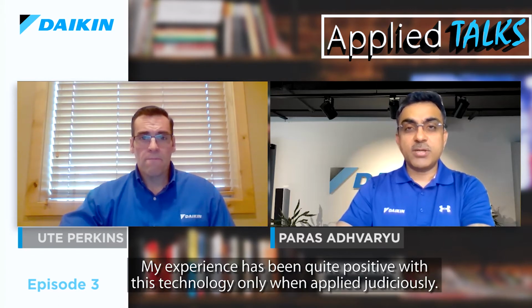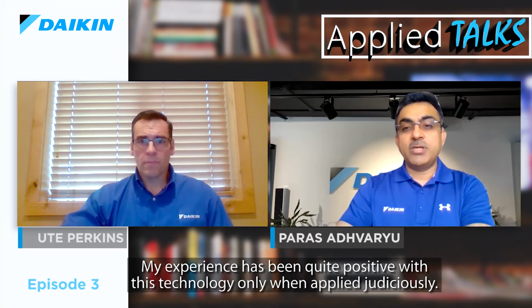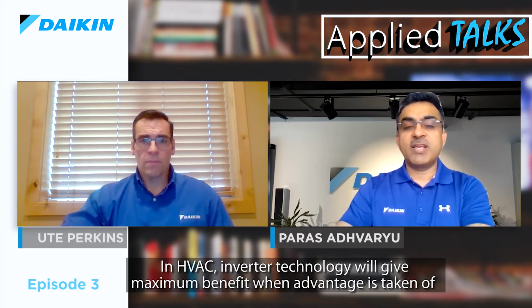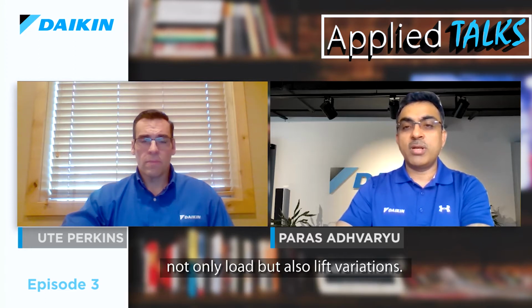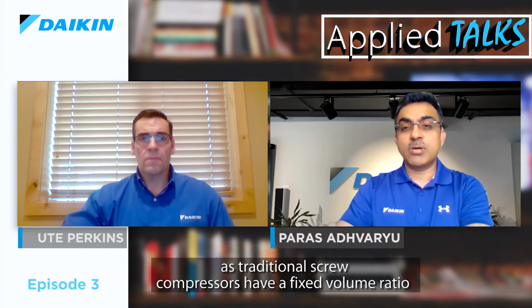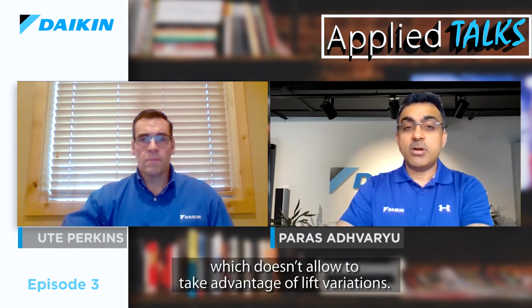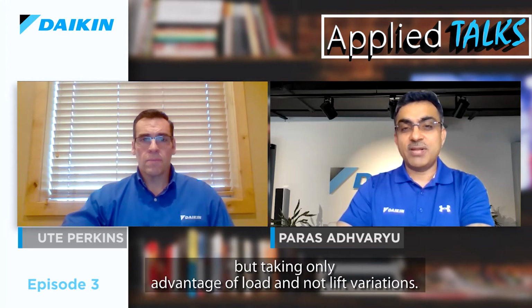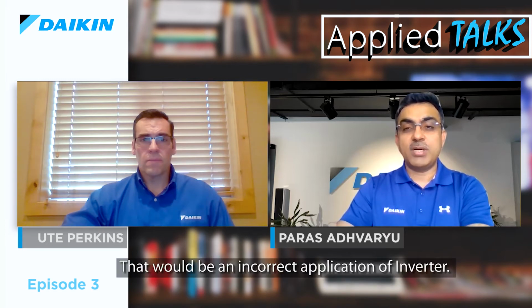Sure. Throughout my career, I have been a vocal proponent of inverter technology in HVAC industry. My experience has been quite positive with this technology only when applied judiciously. In HVAC, inverter technology will give maximum benefit when the advantage is taken of not only load, but also lift variations. Therefore, centrifugal compressors adopted this technology quite faster, but the adoption of inverter technology was quite slow in screw compressors, as traditional screw compressors have a fixed volume ratio, which does not allow it to take advantage of lift variations. There are fixed volume ratio compressors with inverter, but taking only advantage of load and not lift variations. That would be an incorrect application of inverter.